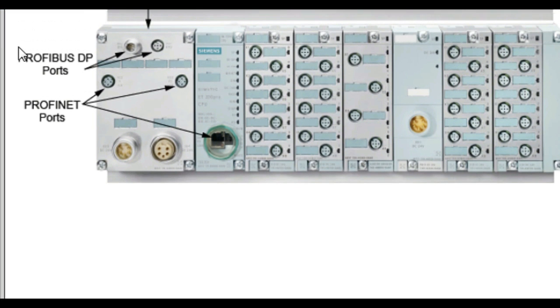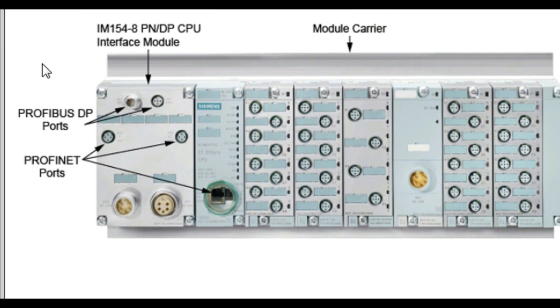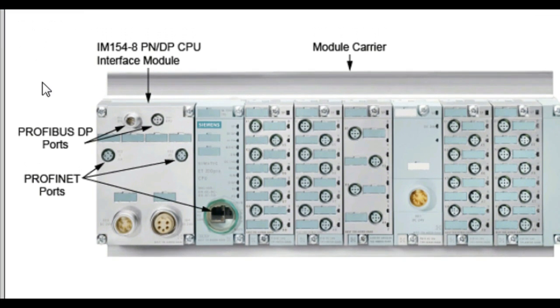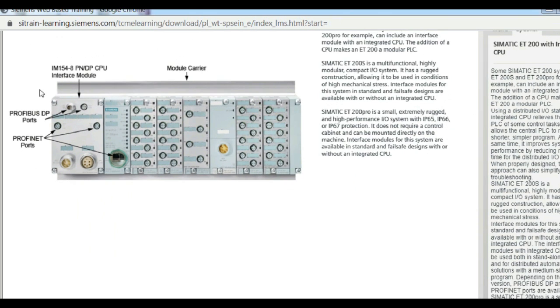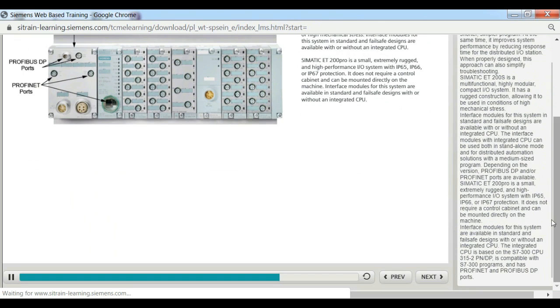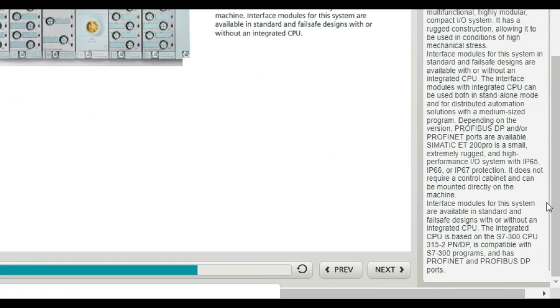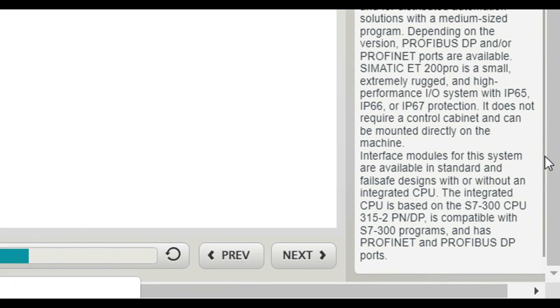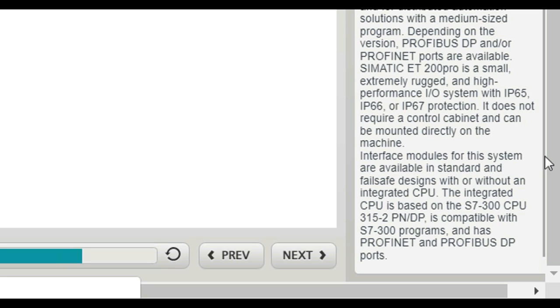Siemens ET200 PRO is a small, extremely rugged, and high-performance I.O. system with IP65, IP66, or IP67 protection. It does not require a control cabinet and can be mounted directly on the machine. Interface modules for this system are available in standard and failsafe designs with or without an integrated CPU. The integrated CPU is based on the S7300 CPU 315-2 PNDP, is compatible with S7300 programs, and has PROFINET and PROFIBUS DP ports.